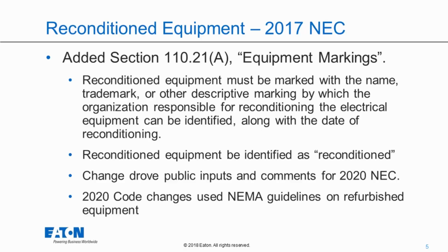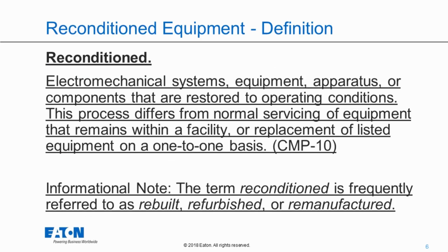That was the first draft and second draft of the 2020 NEC. The primary guidelines they used to identify what could and could not be reconditioned were the NEMA guidelines. If you Google NEMA guidelines on refurbished equipment, you'll get some guidance on what can and cannot be reconditioned. That was primarily used to decide what would be permitted per the 2020 code changes.